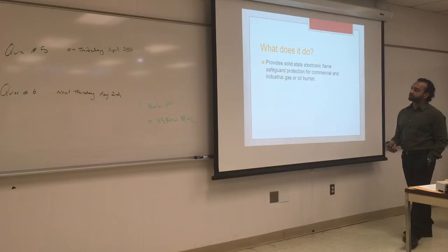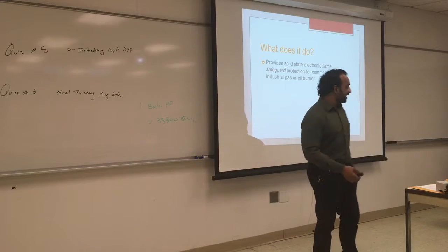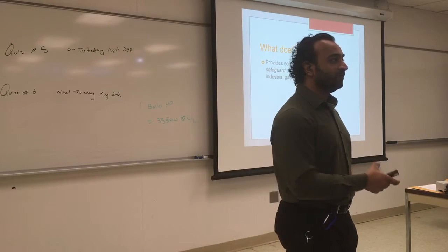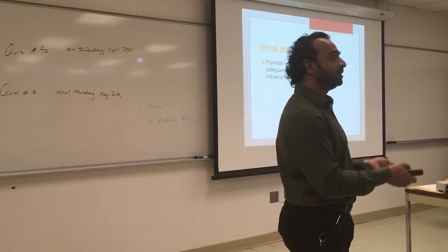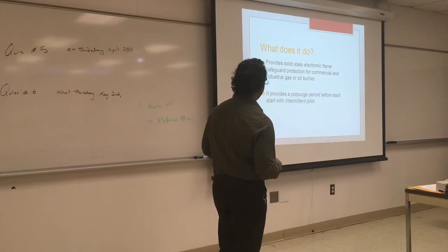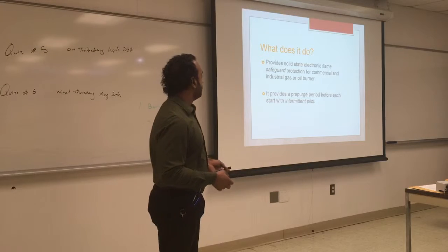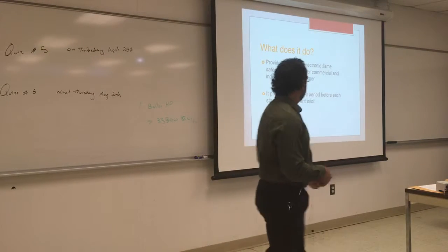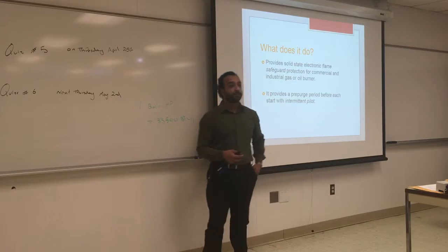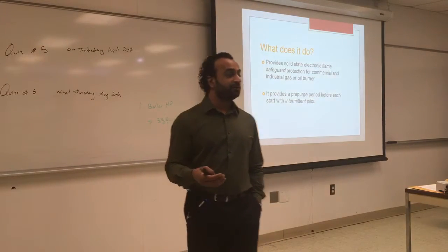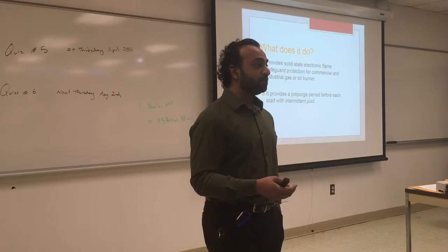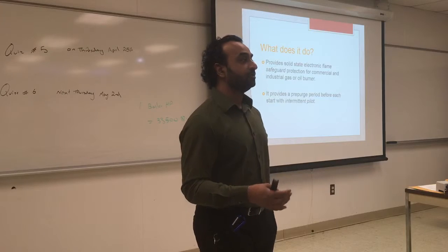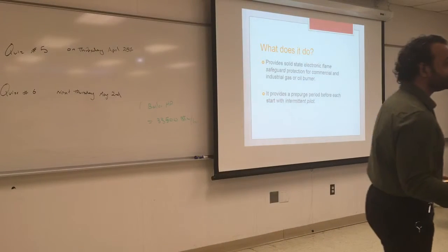It provides solid-state electronic flame safeguard protection for commercial and industrial oil or gas burners. So we can change some of the stuff and the programs in it by changing some of the logic inside. There's a cartridge you can put in and out based on what kind of sequence of operation you need and what kind of fuel you have. It provides a pre-purge period before each start with the intermittent pilot. This pre-purge period is changed based on the size of the chamber.